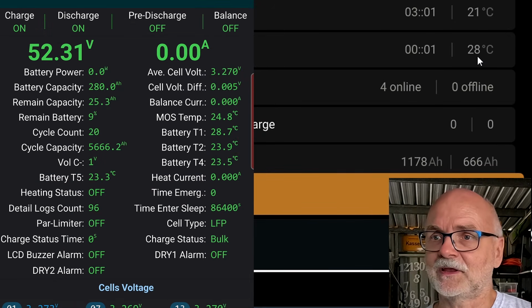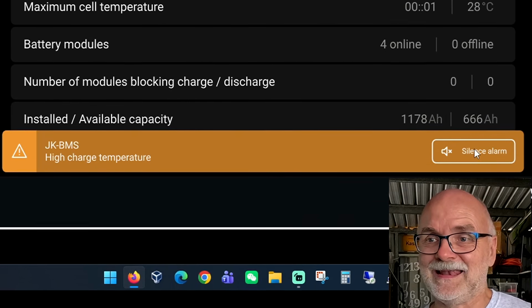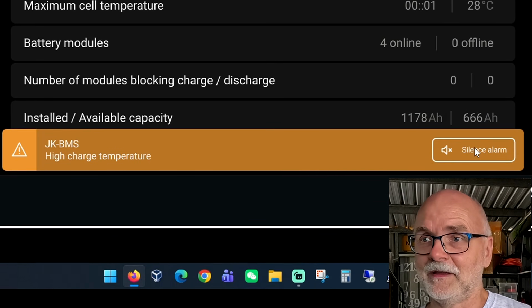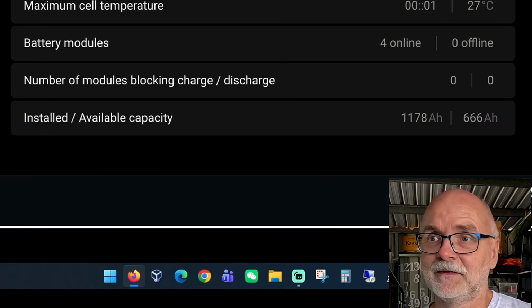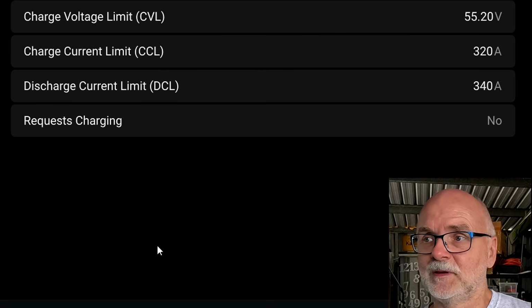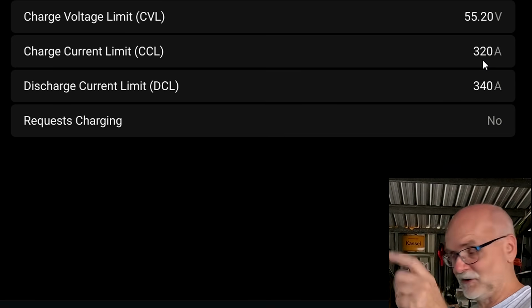Yes, the BMS has already cleared, and it did. Look at this. Nothing is blocking anymore. The alarm is sticky here. I need to acknowledge this one manually. But here under parameters, we should also be back at 320 full power charging again. I'll just heat it up again and you can watch the screen here.